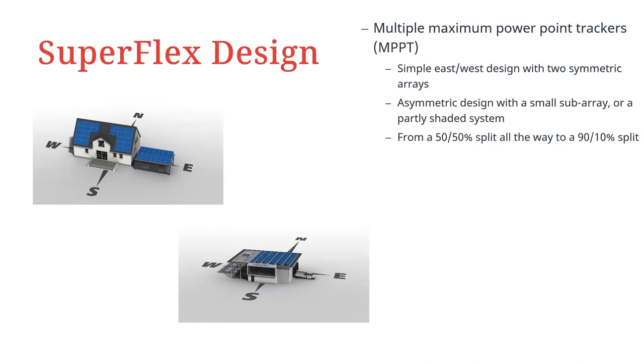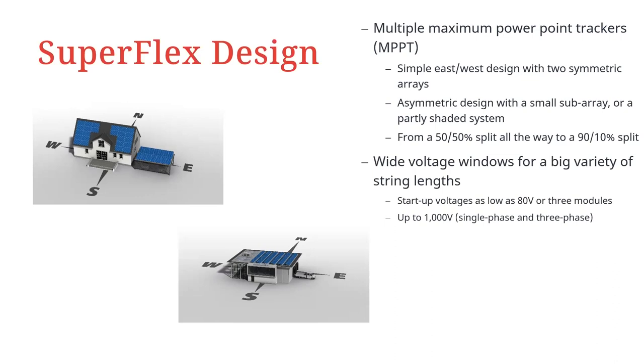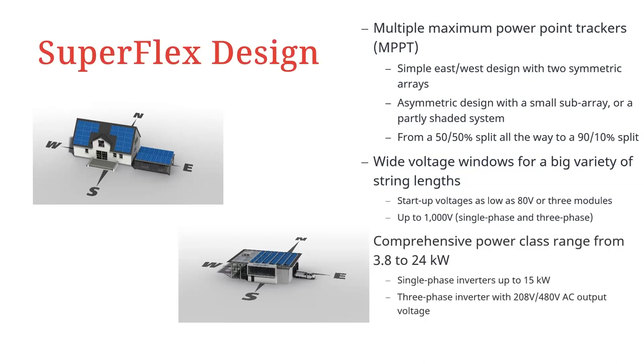The system may be split among the independent trackers as needed — from a 50/50 split all the way to a 90/10 split in terms of power. With the Fronius SuperFlex design, you can design systems from incredibly low startup voltages as low as 80 volts or three modules, all the way up to the maximum DC voltage allowed by NEC code. The Primo single-phase inverter can handle up to 1000 volts in non-residential applications, allowing for a maximum number of modules in one string and a reduced balance of system cost.